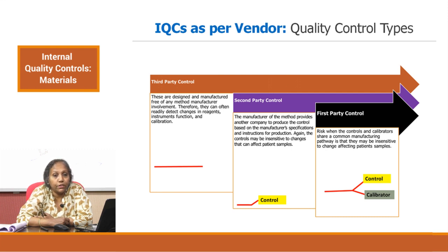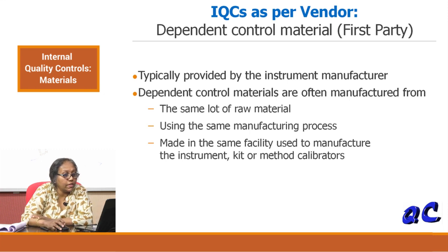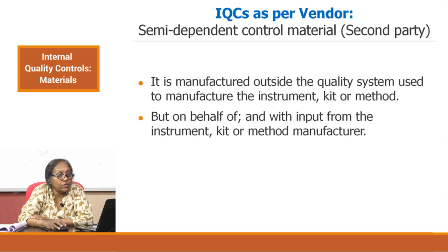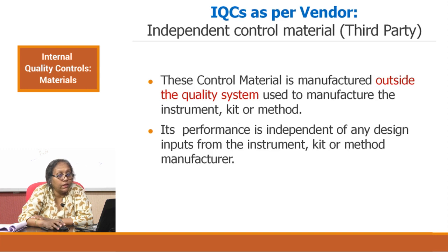Another classification of controls is as per vendor: first party, second party, or third party controls. First party controls, also called dependent control materials, are typically provided by the instrument manufacturer. They are often manufactured from the same raw material lot, using the same manufacturing process, and made in the same facility used to manufacture the instrument kit or method calibrators. Second party controls, or semi-dependent controls, are manufactured outside the quality system used to make the instrument kit or method, but are manufactured on behalf of or with the input of the instrument or method manufacturer. Third party controls, or independent control materials, are manufactured entirely outside the quality system of the instrument kit or method manufacturer.